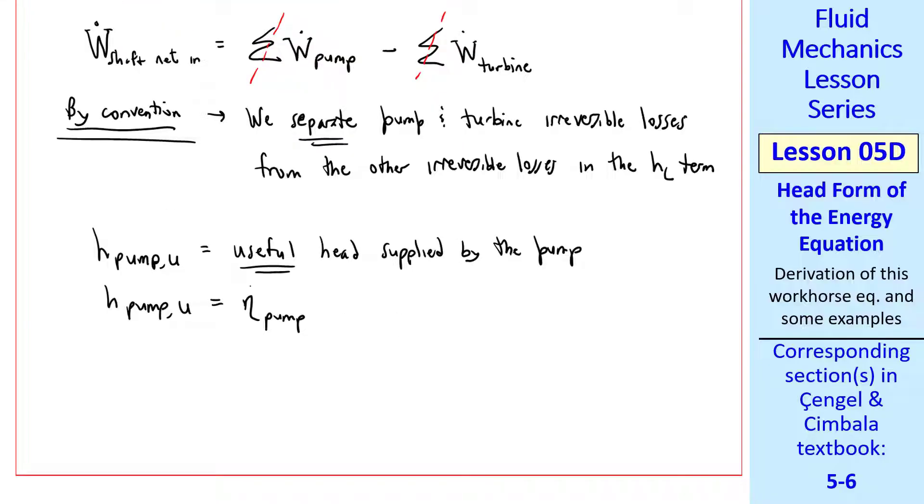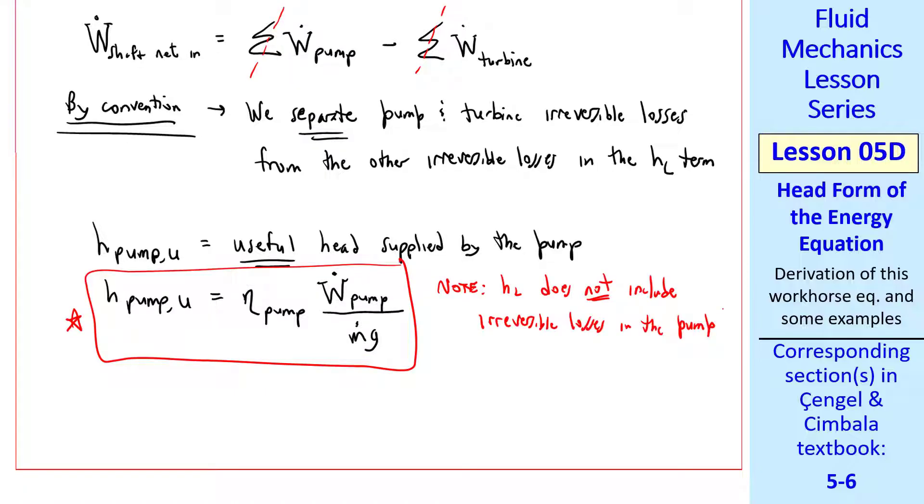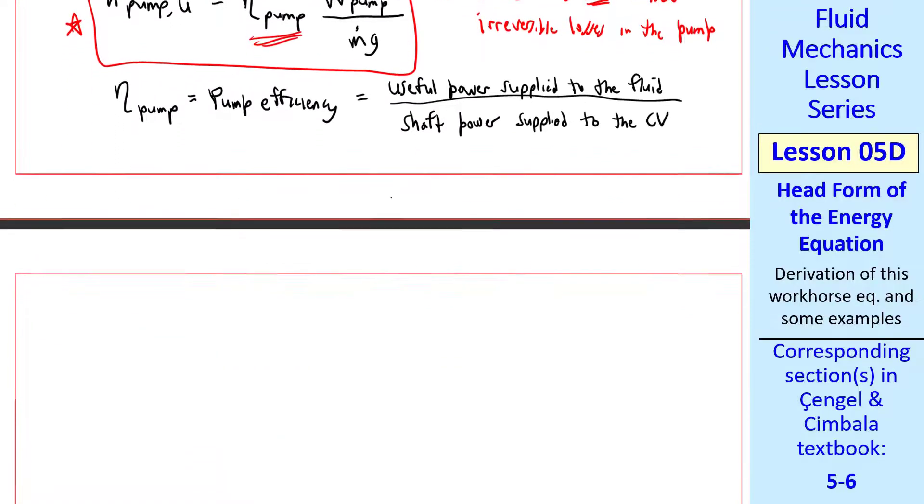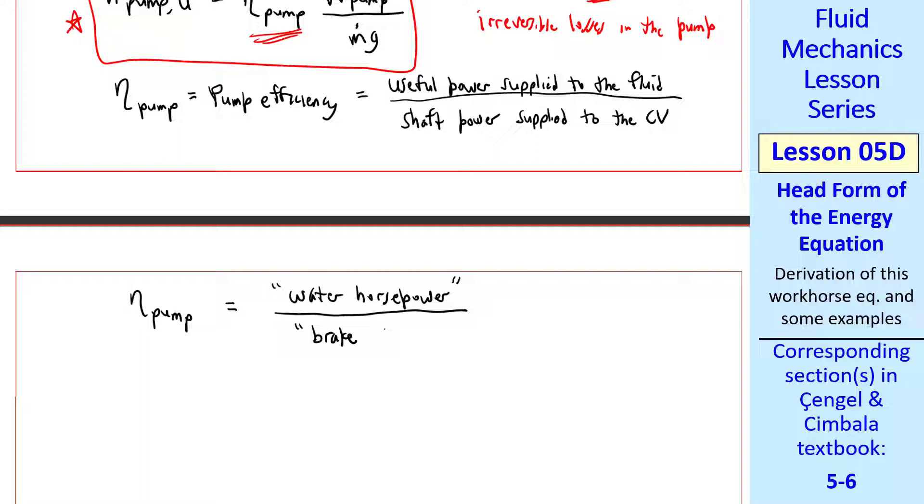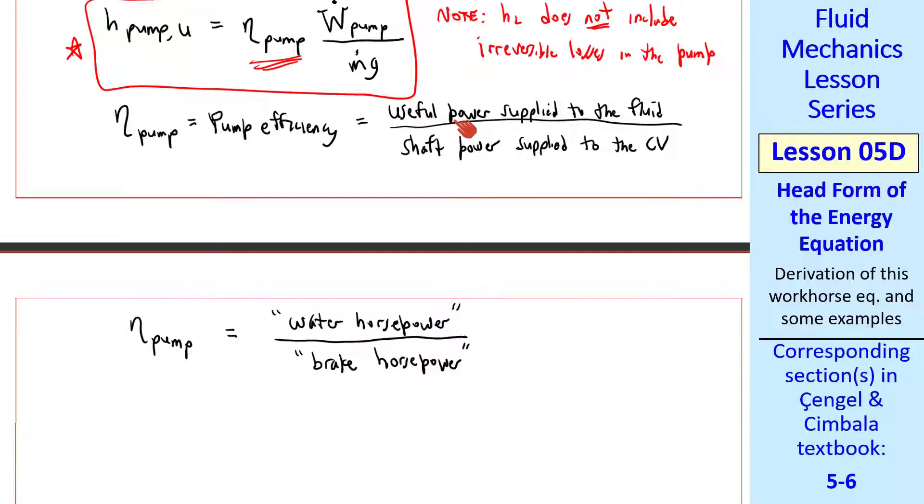Here's how we'll do that. We'll define H pump u as the useful head supplied by the pump. And we'll define a pump efficiency, eta pump. So H pump u is eta pump, the shaft power of the pump, W dot pump divided by M dot g. Note that there's an efficiency because there are irreversibilities in a pump. But we note that HL does not include irreversible losses in the pump. We're treating those separately by defining an efficiency of the pump. Eta pump is the pump efficiency, which we define as the useful power supplied to the fluid divided by the shaft power supplied to the control volume. In turbomachinery parlance, they call the numerator water horsepower and the denominator brake horsepower. This terminology is used even if the fluid is not water, but I prefer to call it useful power, hence the subscript u. Like any efficiency, eta pump has to be less than 1.